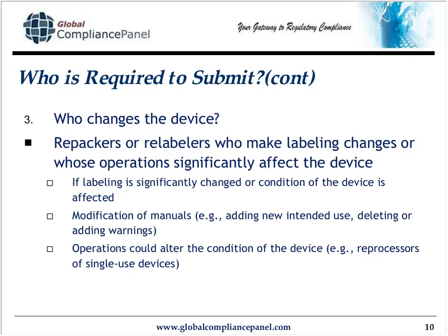If they're modifying the manuals, maybe they're adding a new intended use, and we'll talk a little about intended use in a little while. If they're deleting or adding warnings, or their operations could alter the condition of the device. In some cases, it's medical facilities such as hospitals. However, there are private firms out there that reprocess single-use devices and then resell them. These firms are significantly changing a device enough that they do need to submit a 510K.